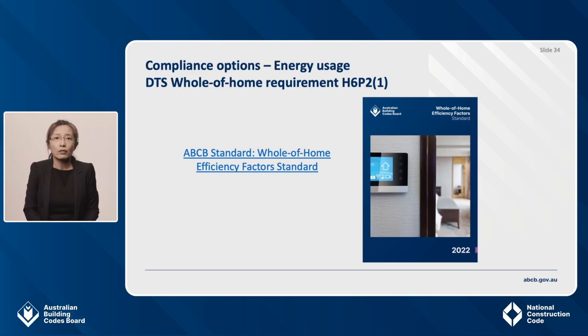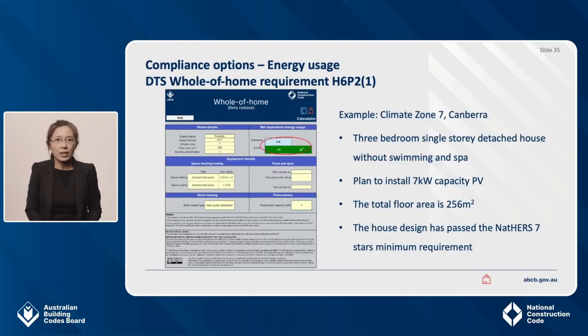Before giving an example for the whole-of-home calculator, I'd like to show you the whole-of-home efficiency factor standard, which can be accessed from the ABCB website. Here is an example using the whole-of-home calculator. The heating and cooling uses a heat pump, and the water heater uses an off-peak heat pump. Together with a 7 kW PV system to offset, the net equivalent energy usage is kept below the allowance of 5.8 kW of PV capacity. Please note that installed PV (ER) is not mandatory. You could meet the whole-of-home requirement without PV if the net equivalent energy usage calculated in accordance with A is not greater than the energy usage allowance B.